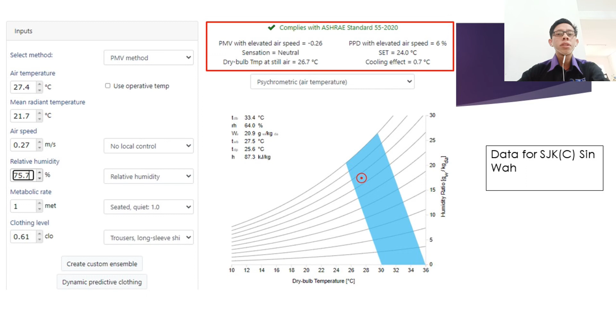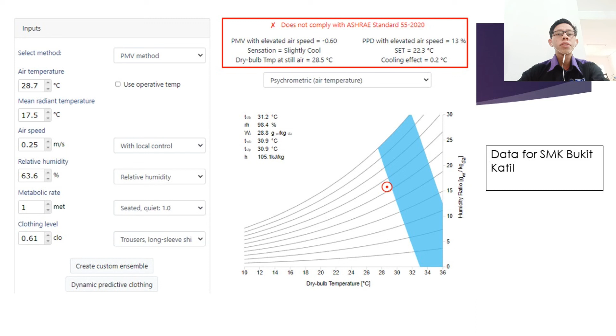Based on this picture, the PMV shows the value negative 0.60 with elevated airspeed, and PPD shows the value 13%. It shows the classroom at SMK Bukit Katil at 12:30 p.m. is slightly cool. For the victim, they only sit, so it does not comply with ASHRAE Standard 55. But if the victim does some activity, the thermal condition will be comfortable. As the red dot is a little out of the blue zone, the space is slightly cool for the victim while they are sitting.